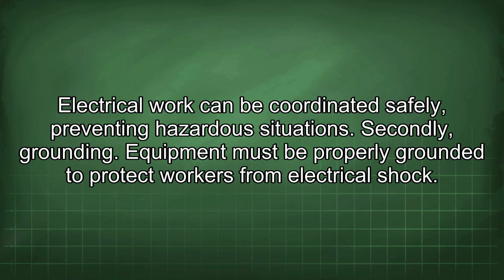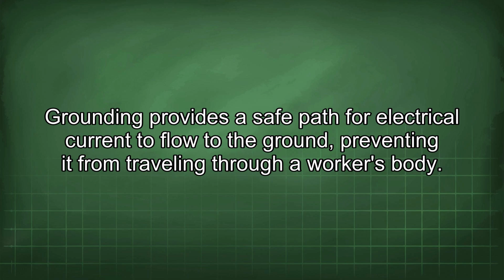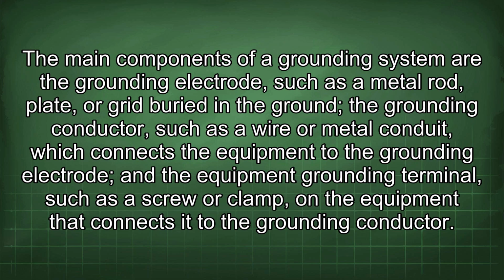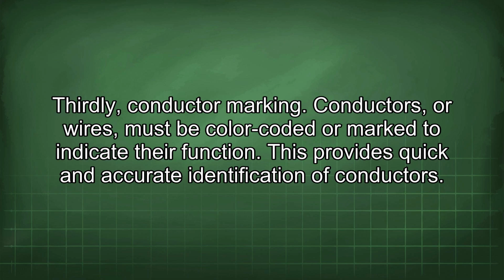Secondly, grounding. Equipment must be properly grounded to protect workers from electrical shock. Grounding provides a safe path for electrical current to flow to the ground, preventing it from traveling through a worker's body. The main components of a grounding system are the grounding electrode, such as a metal rod, plate, or grid buried in the ground, the grounding conductor, such as a wire or metal conduit which connects the equipment to the grounding electrode, and the equipment grounding terminal, such as a screw or clamp on the equipment that connects it to the grounding conductor.